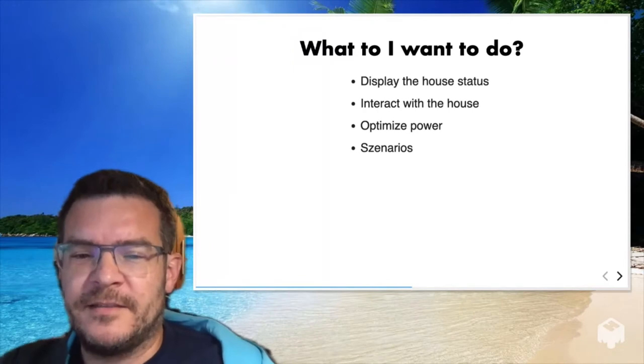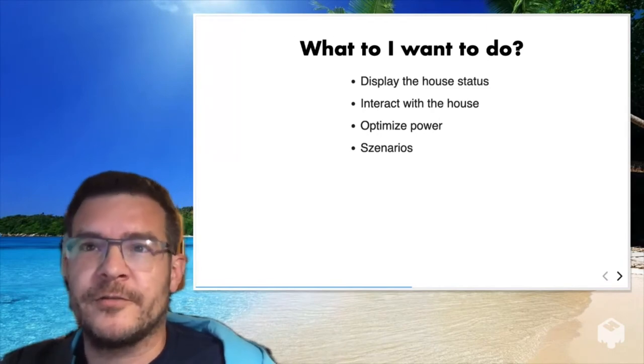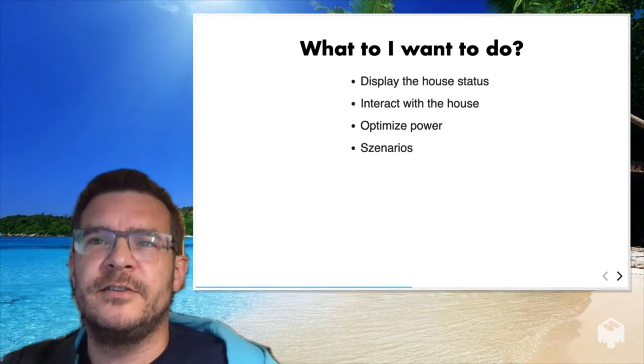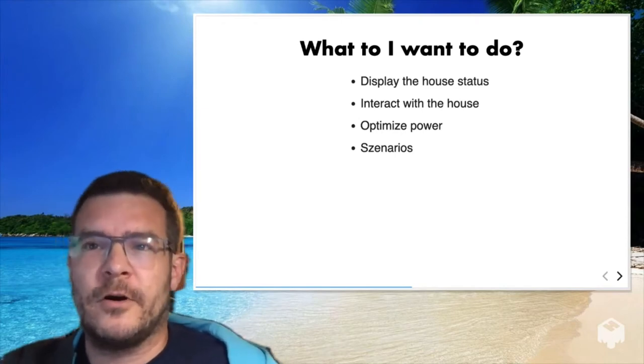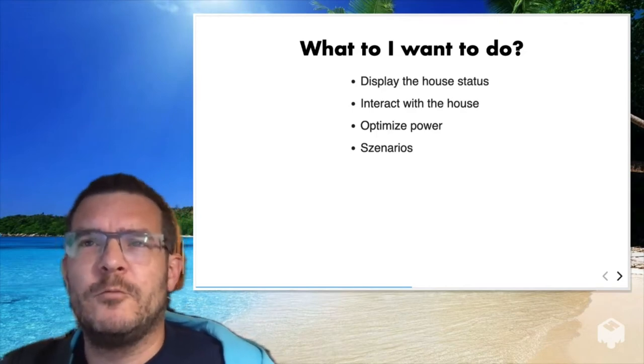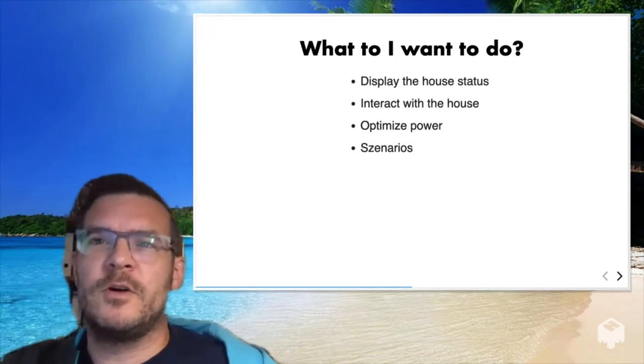turned on. So one of the things I would really like to do is, as soon as a smoke detector goes off, turn on all the lights, open all the shutters. If there is a real fire and you don't know how long the electricity will be able to continue, it's really important that the fireman can enter through a window or can evacuate you through a window. And especially, I showed you those little room controllers. So I want, as soon as one smoke detector goes off, that these little controllers have in text glowing in there which one went off.